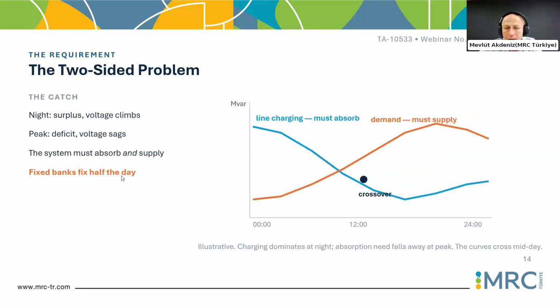Let's take another two-sided problem, the line charging, the 180-degree out of phase reactive power problem in a typical grid, the night surplus and the peak deficit. So the long lines, I think it is the case for Uzbekistan in the western part of the country. So we have long lines in the light load case.